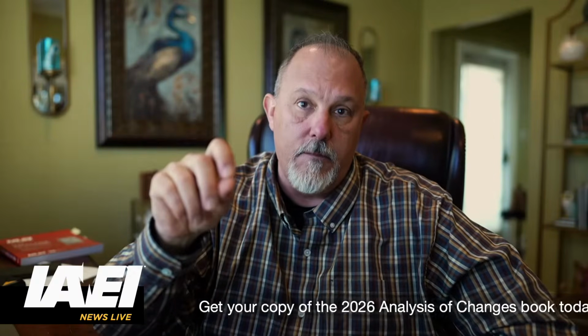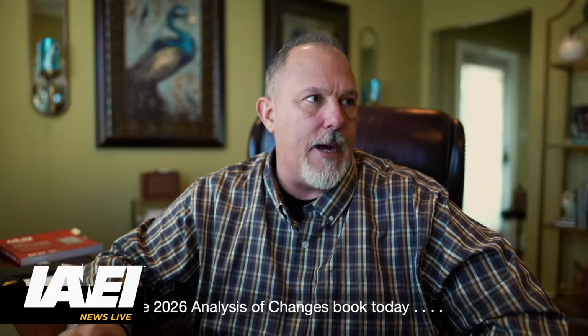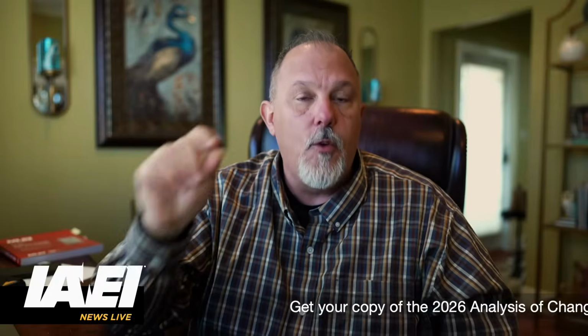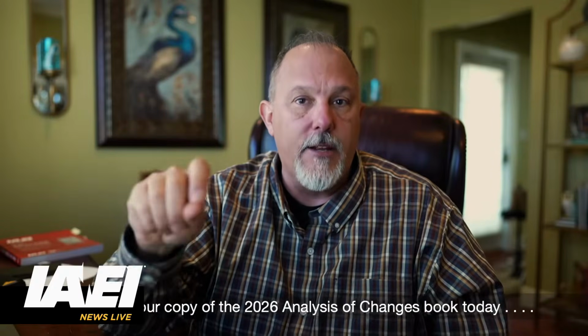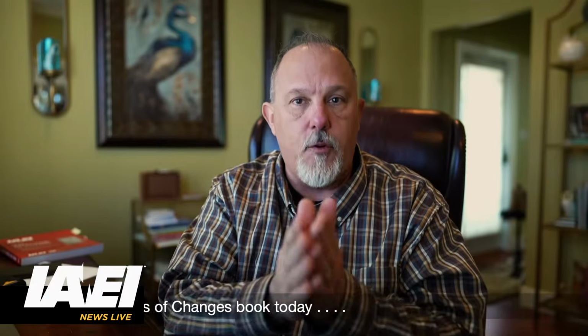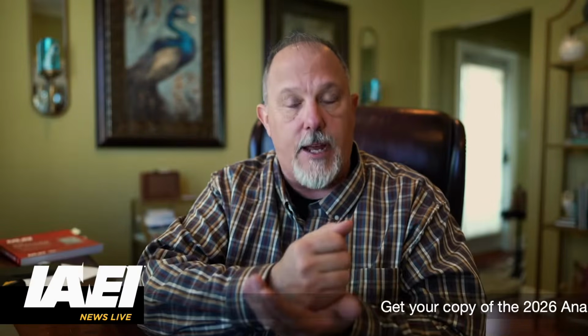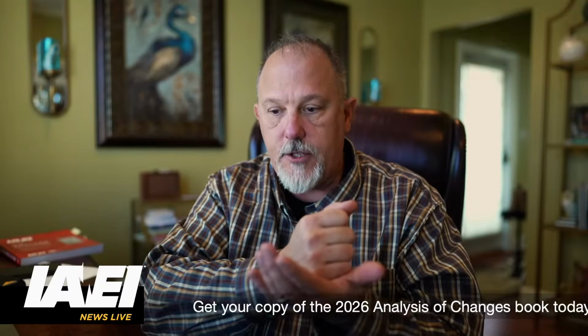All right, so "suitable" was replaced with "identified." Now, "identified" is a defined term. And if you think about how we use the word identified in other places in the code, handle ties are a great example. We tell you you need to have an identified handle tie whenever you take two single pole breakers and use those on a shared neutral application. We require you to have an identified handle tie on those two breakers.